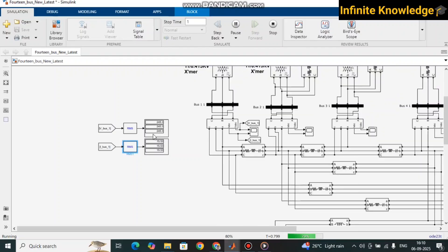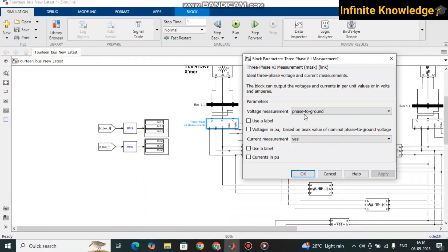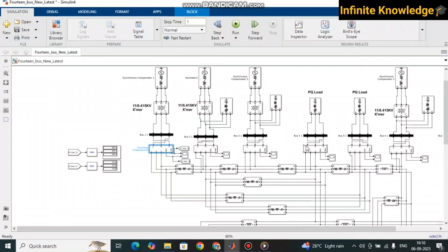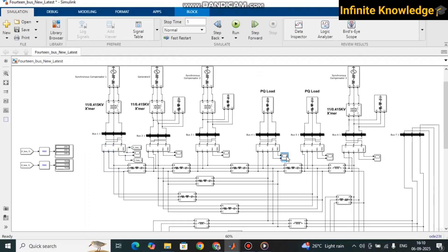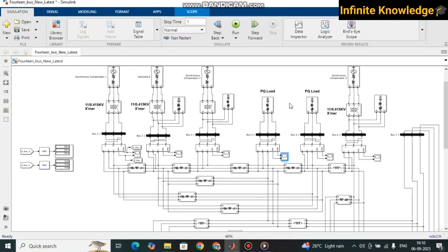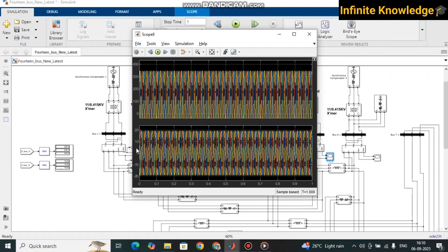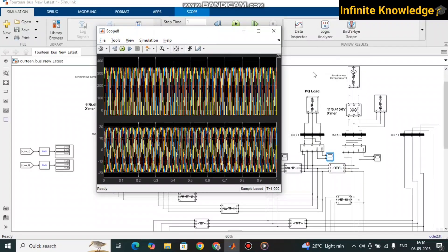We are getting 245 V, which is a single-phase voltage. I am measuring bus number one, and we are measuring phase-to-ground voltage. For this specific bus you can see the voltage and current — current is 10 amperes. As per the load, there is some load variation for this PQ bus, where the current is 20 amperes.